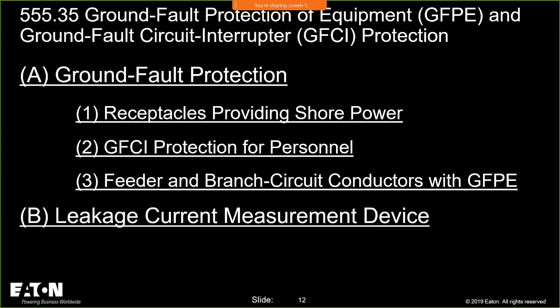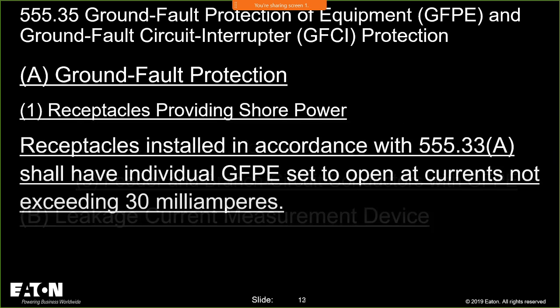We have 555.35 A and B now. A talks about ground fault protection, receptacles providing shore power, GFCI protection for personnel, and then feeder and branch circuit conductors with ground fault protection of equipment. There is a big difference between GFPE and GFCI.